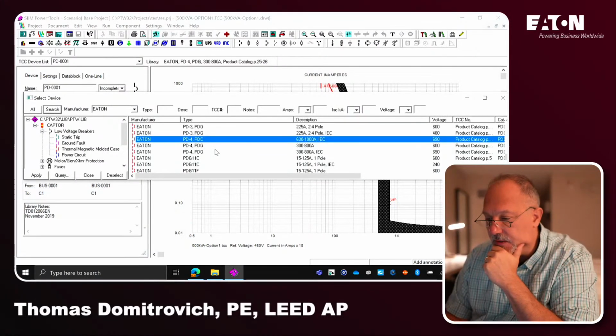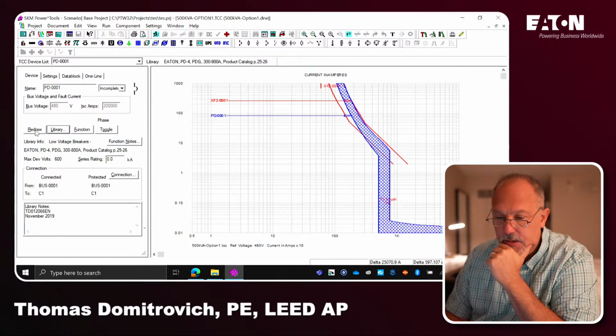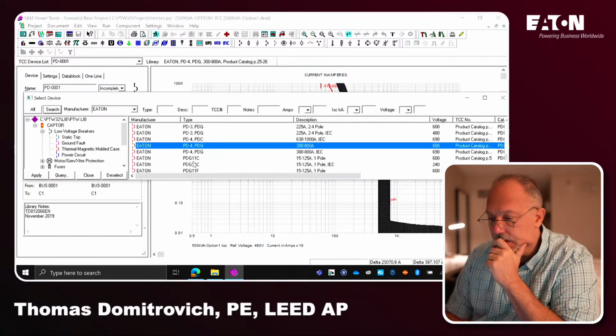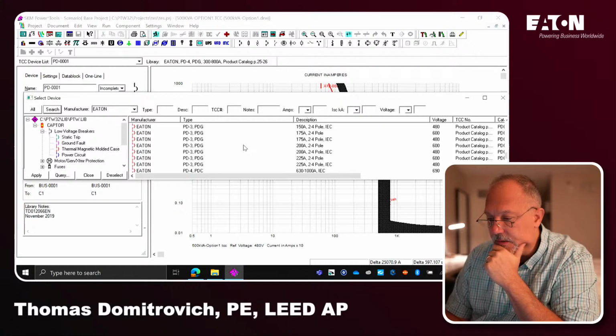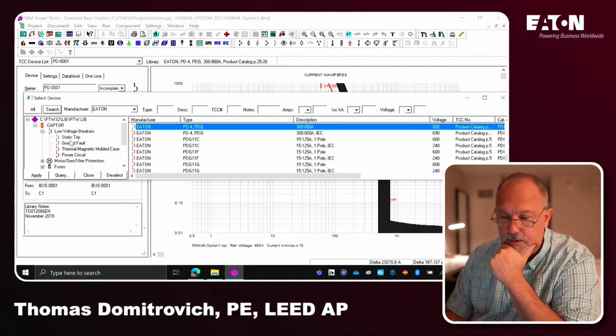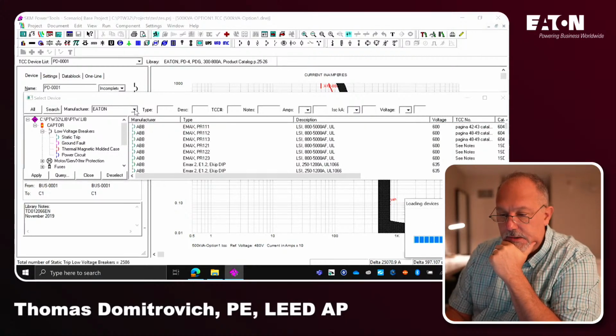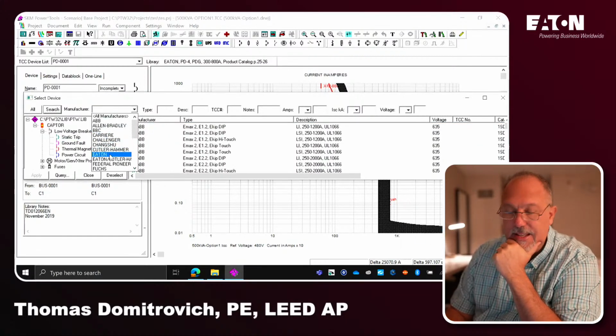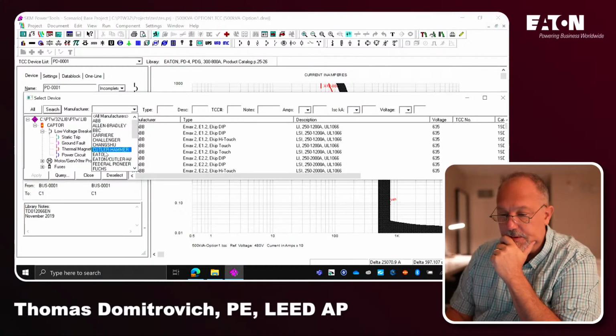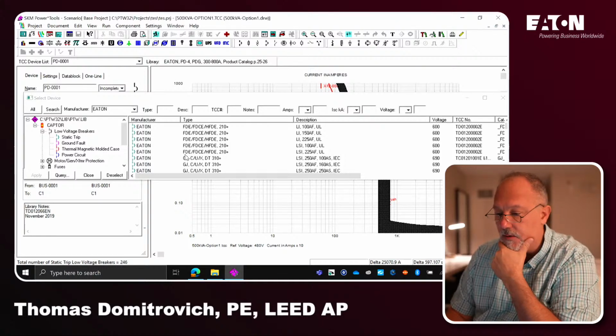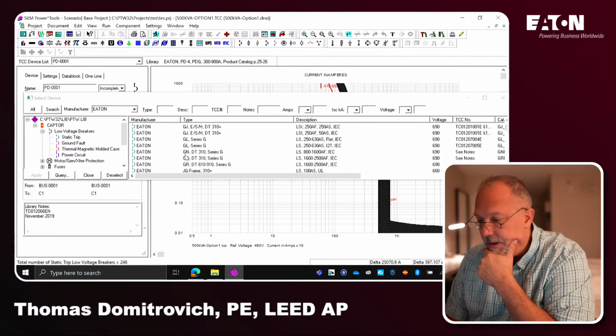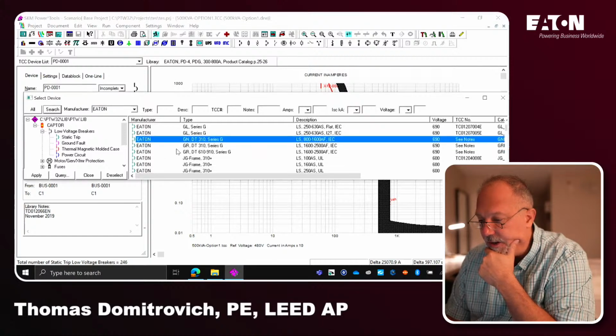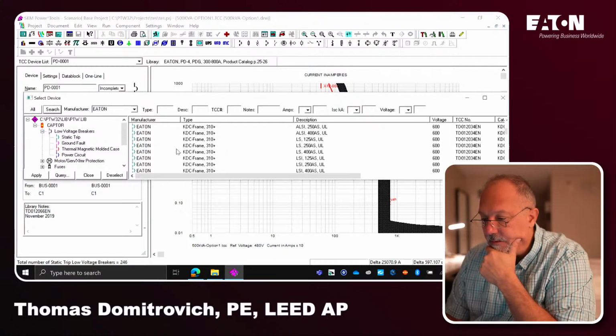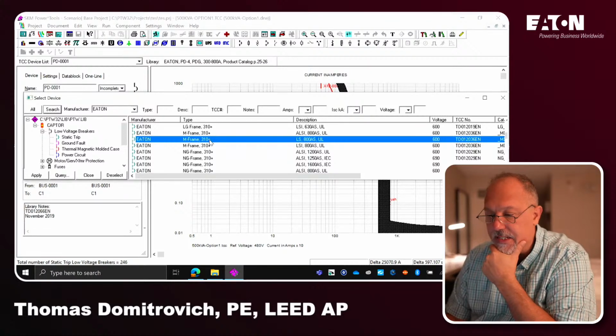that's IEC. Whenever you see IEC, that's international standards. Whoa. Library. I need a breaker, so I'm going to put in an electronic trip unit. I'm going to go to static trip, and you always have to pick Eaton. Remember, that's the only way it'll work correctly. Here's an 800. That's a GL. I don't like that. 800. Here we go. LS. It's a fixed instantaneous.